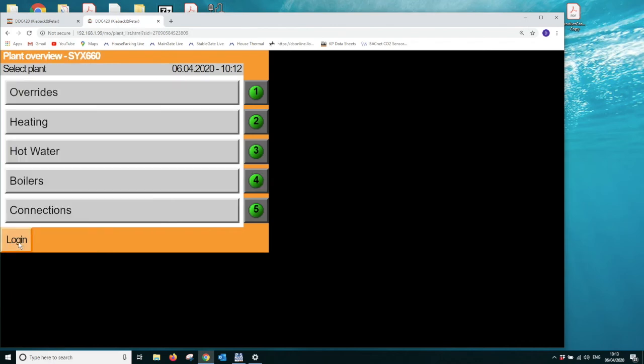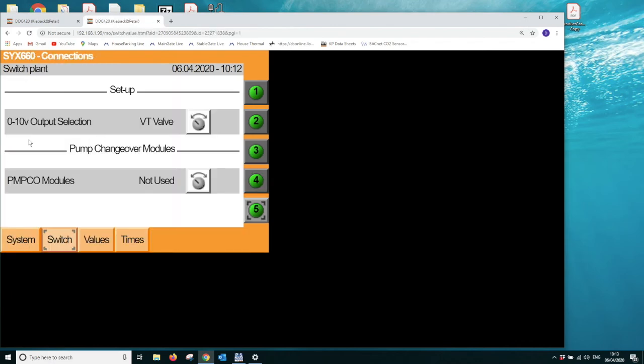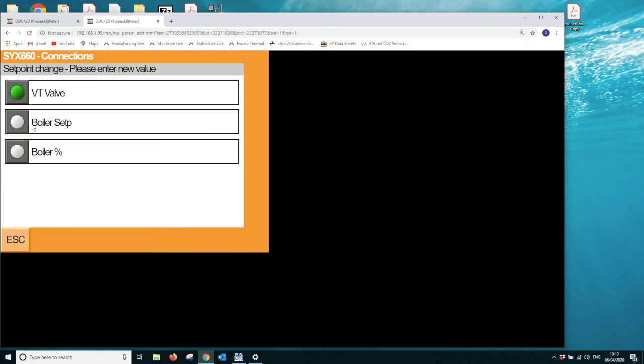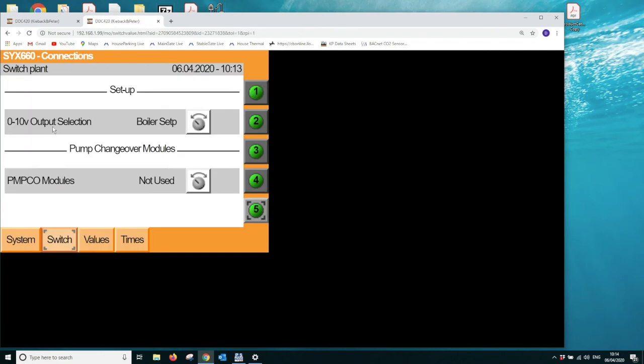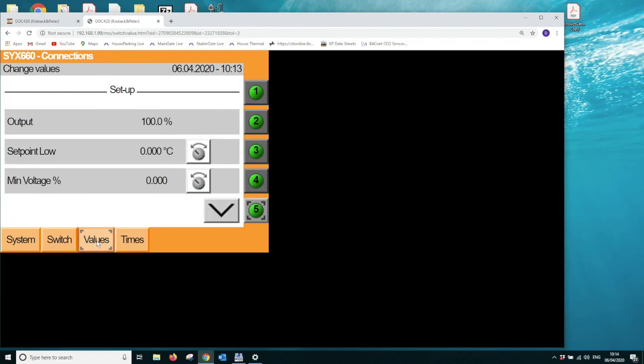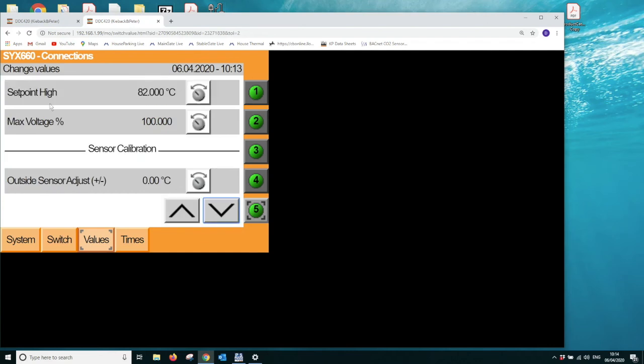We now click on system and we go to connections. If we're going to be utilizing the 0 to 10 volt output, we can choose what that output is used for. In this default condition, it's the VT valve. If we wanted to use it for boiler demand or a Boiler Pro, we would select boiler percentage. If we wanted to have the boilers driven from a 0 to 10 volt signal for a set point, then what we could do is select boiler set point, and then we can choose values, and we can set up the set point low and the corresponding voltage that we require, and we can do that from the set point high and the max voltage that the boiler would accept as well.